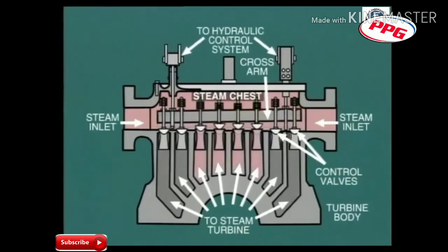These control valves are set in such a manner that only one valve at a time is actually throttling steam, while the others are either fully open or closed, depending on the actual load.